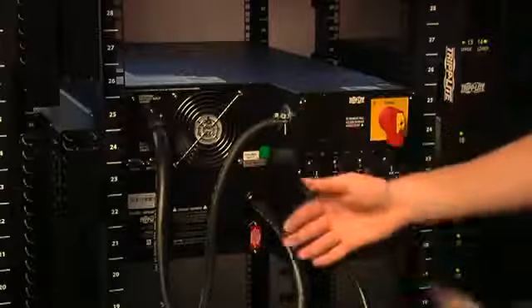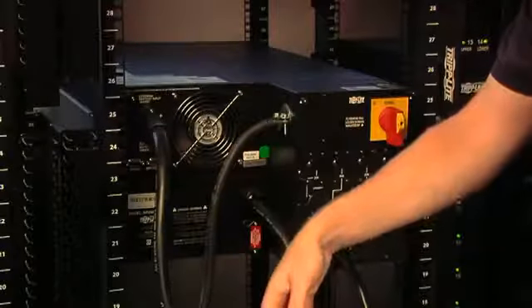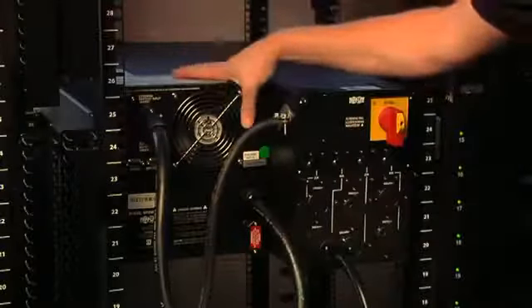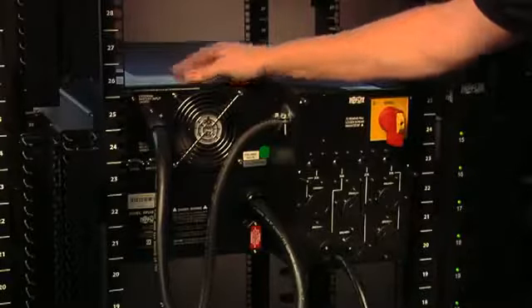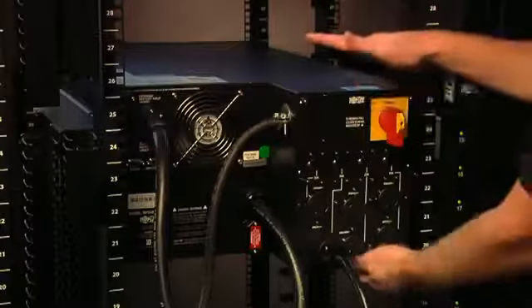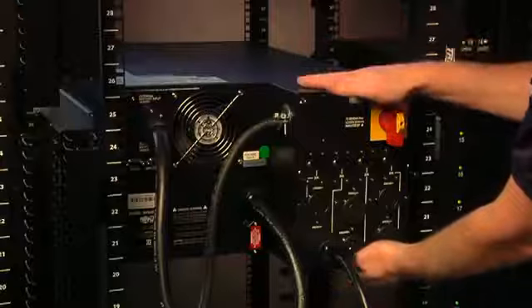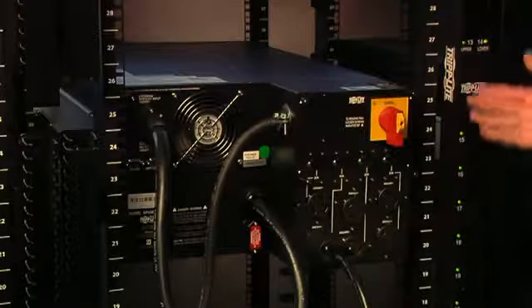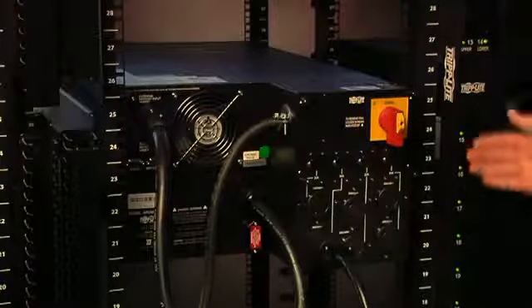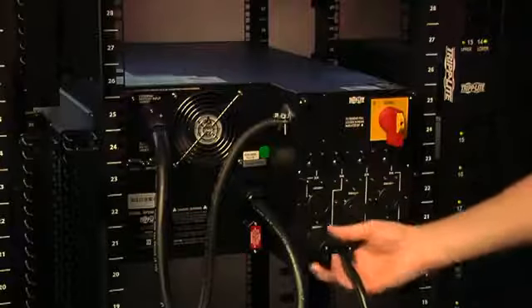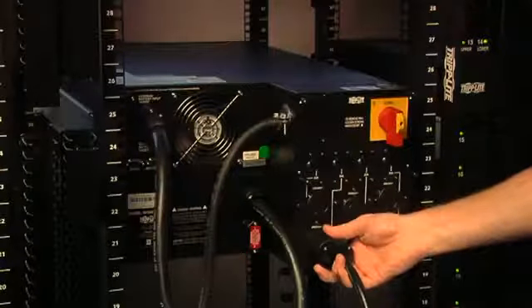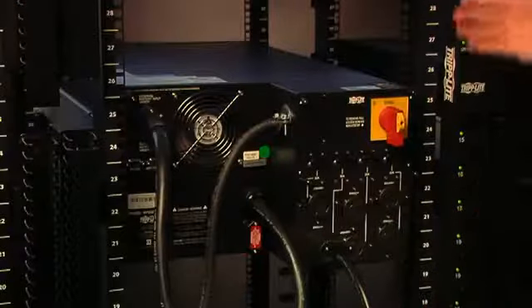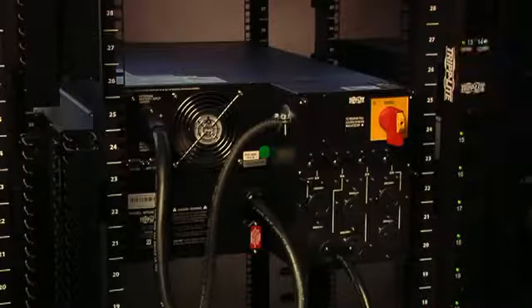Okay? To replace the system, first we would take the battery connection out because this power module needs service. So we disconnect that, and then we're going to show you how to hot swap this without downing the load. In this case, for demonstration purposes, we have lights on a PDU connected to an L630 receptacle here, and throughout the process these lights will remain powered and active.